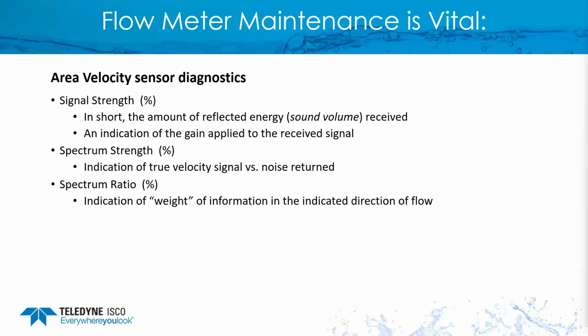And this could be an indication of when you need to go out and do maintenance and clean your channel or the sensor. Because if the trend is normally around 90 to 100%, and then all of a sudden you see it starting to decline down to 60 to 40%, that may be your trigger when to go out there and clean off debris.